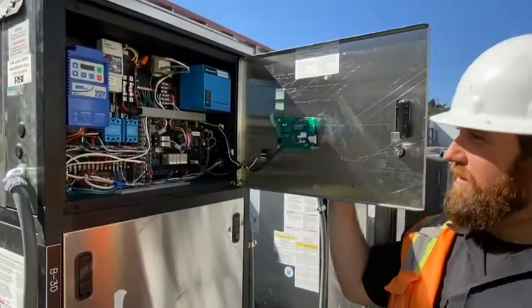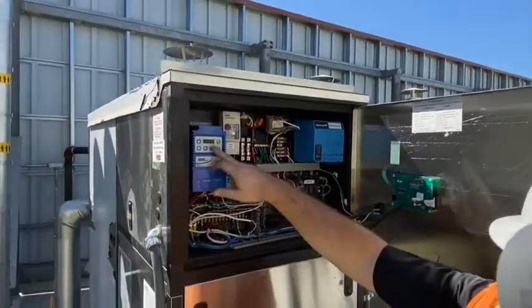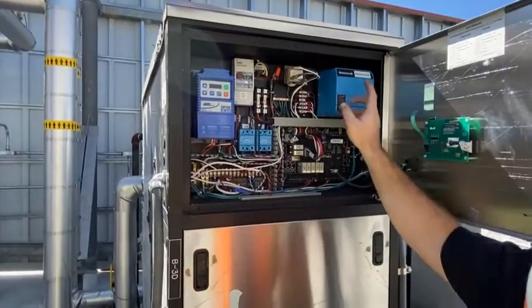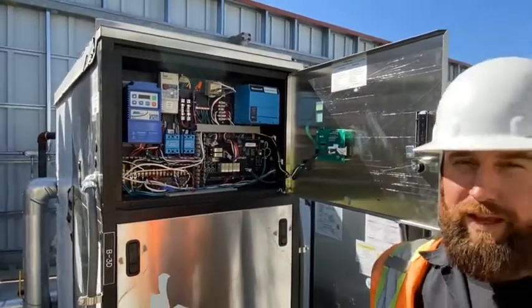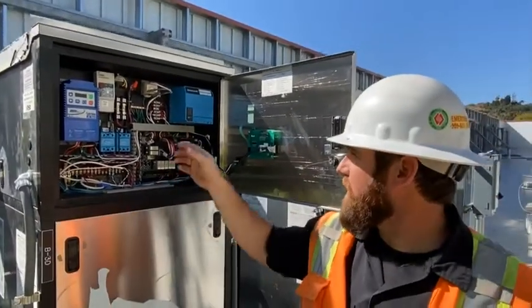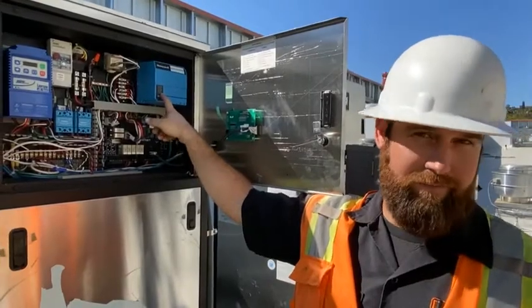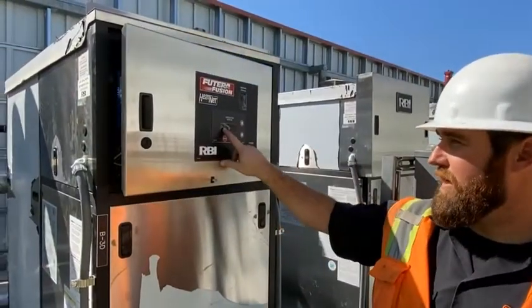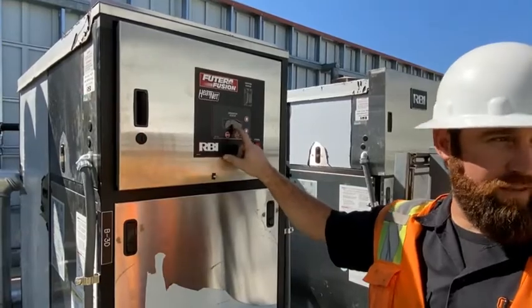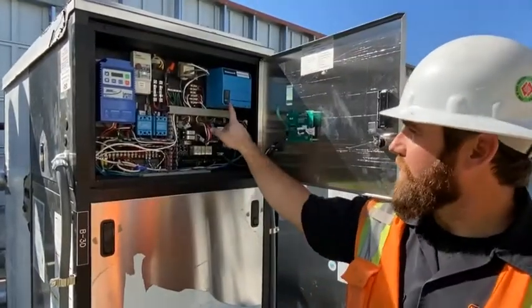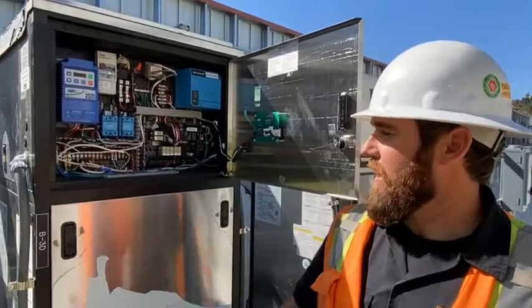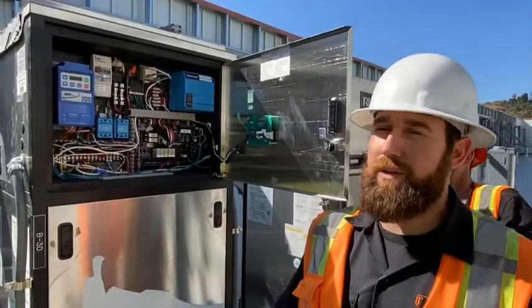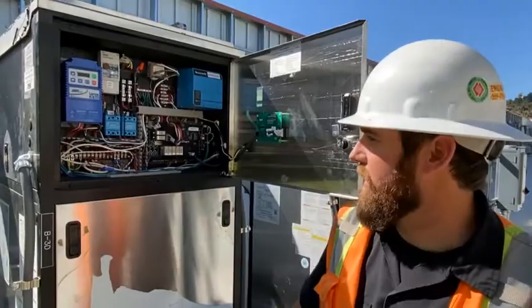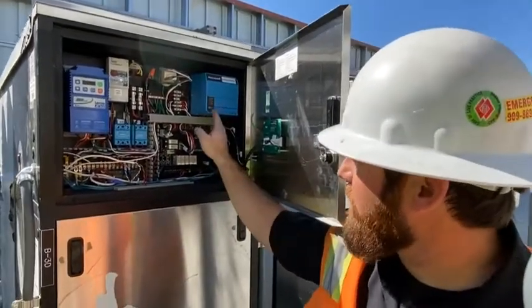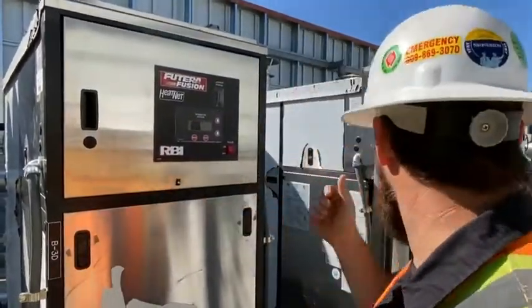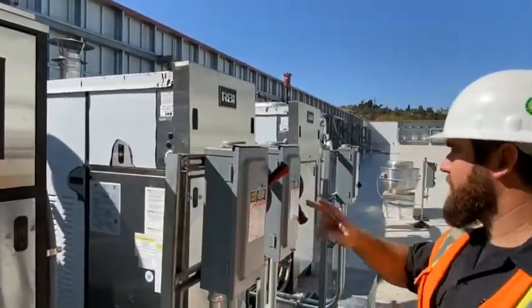So inside here, we've got our fan VFD, which is not running right now, we're at load. We've got our Honeywell burner control. If you have any flame failures, pilot flame failures, this alarm light is going to turn on red. You'll also see an ignition control alarm on this front panel here. So you hit the reset button, it resets. If it continues to fault with the same issue, then you want to contact us to come out and take a look at it. So that's our first safety. We also have the main power disconnects here, 1, 2, and 3.